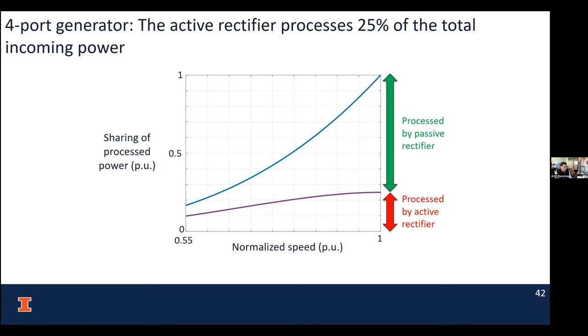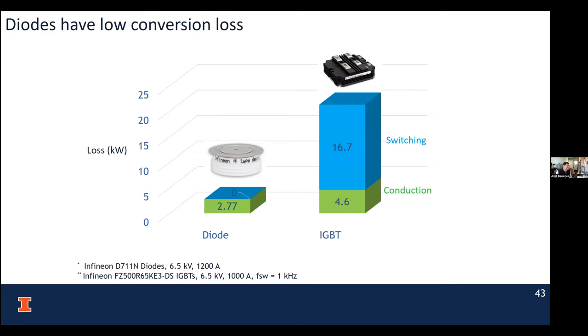Now let's look at the loss. Since I'm processing less power through the active rectifier, I can eliminate most of the switching loss -- I don't have to deal with the switching loss of the IGBTs. What I'm left with is processing the majority of the power through the diodes, and these diodes operate at line frequency, not switching frequency. We're talking about a 20 hertz signal going through these diodes, so we can drastically reduce the loss in the converter since we're processing less power.